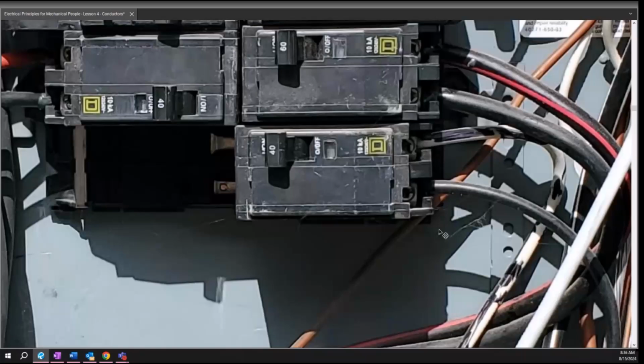It heats up. Gotcha. You have increased resistance between the conductor and the terminal. You get I squared R loss, so you get lower voltage on the conductor, which then increases the current because more power is required. It's essentially a runaway, just long term. Months, years. This will start heating up and start melting. Gotcha.